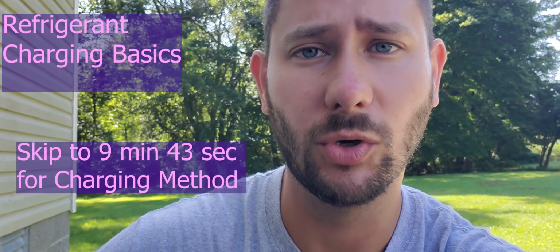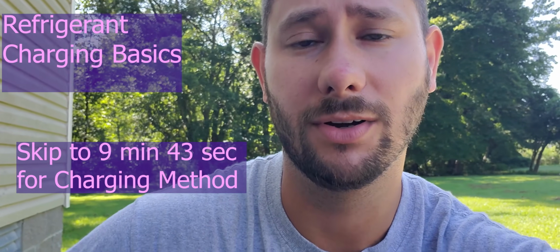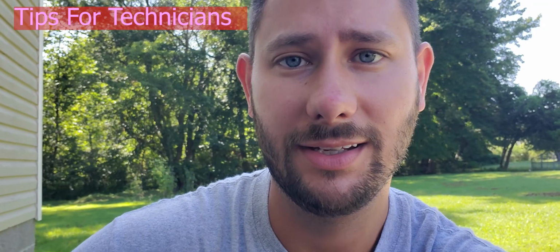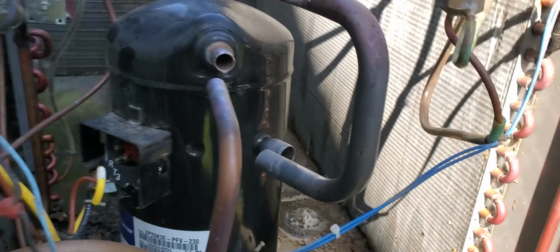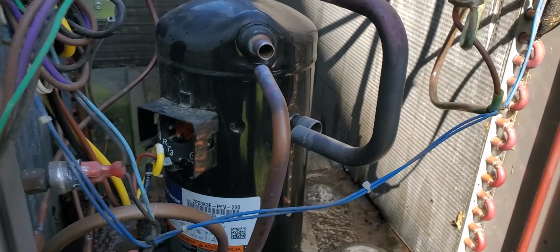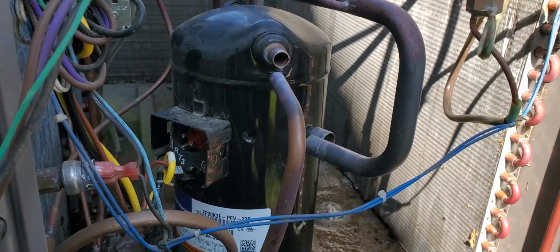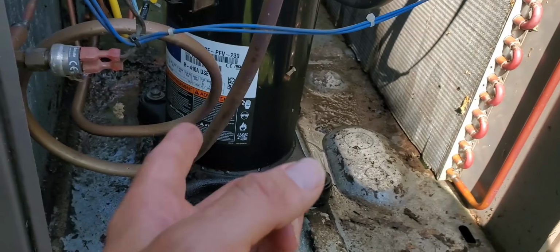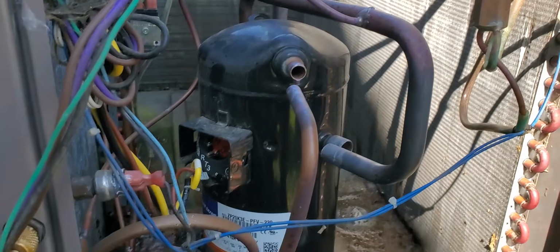I'm replacing a compressor, a coil, an indoor coil, and an outdoor fan motor on the same package unit. Yeah, it's a lot of failures on one unit. Let me show you. Just used the torches and unbrazed the suction and discharge line from the compressor here. I'm going to take this compressor out now.